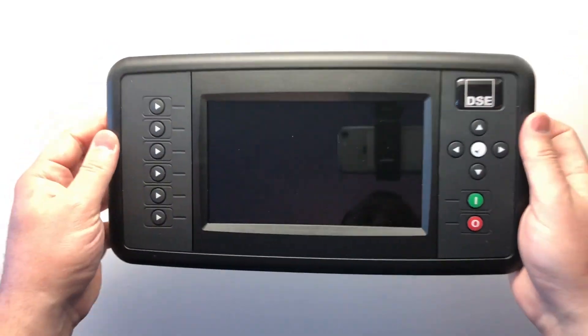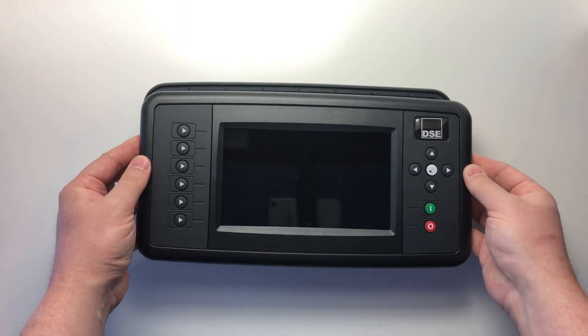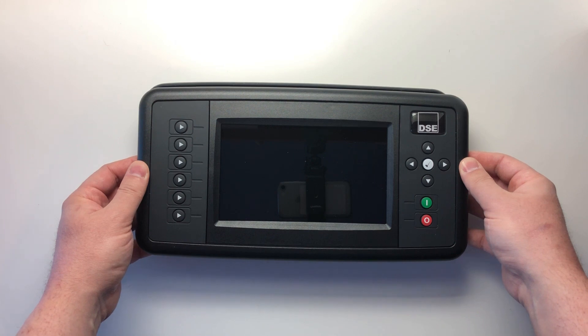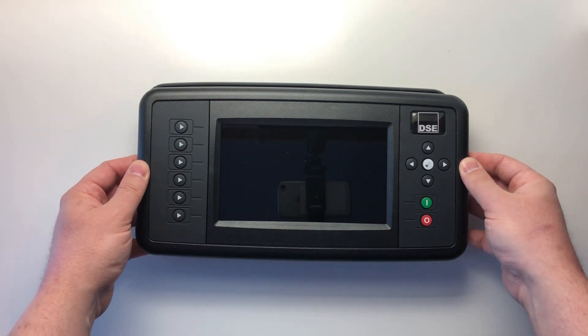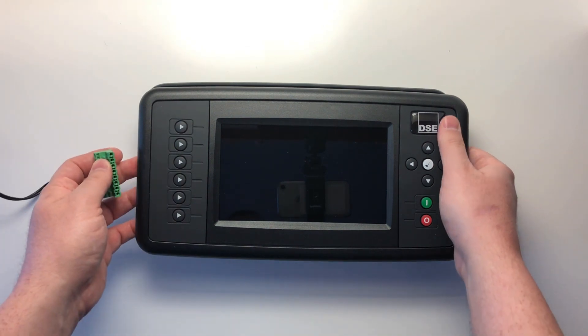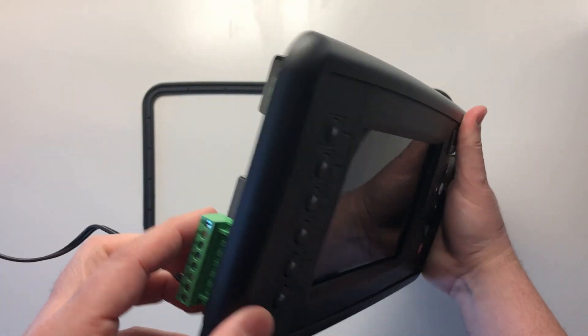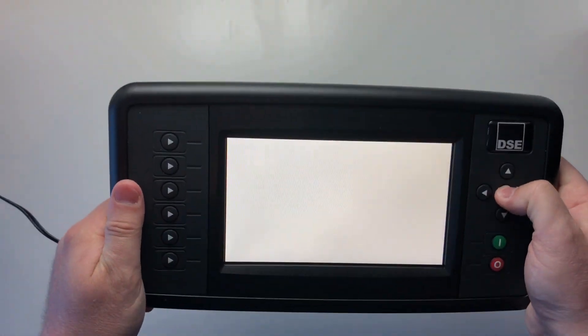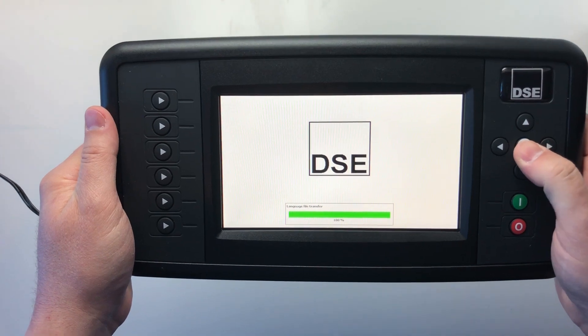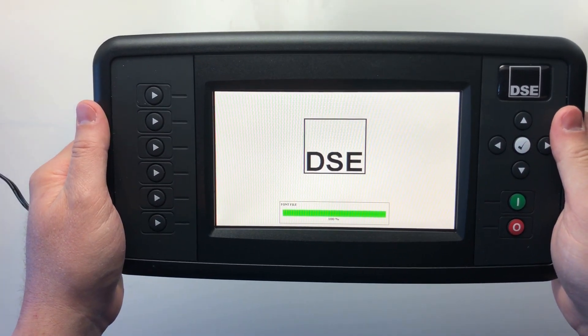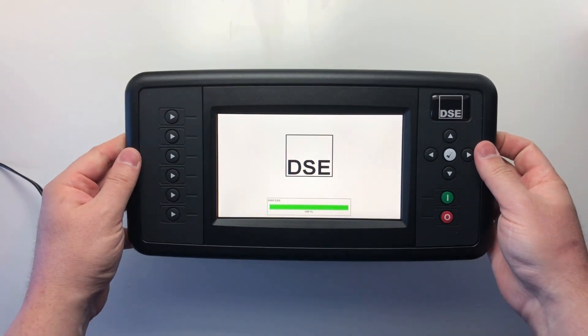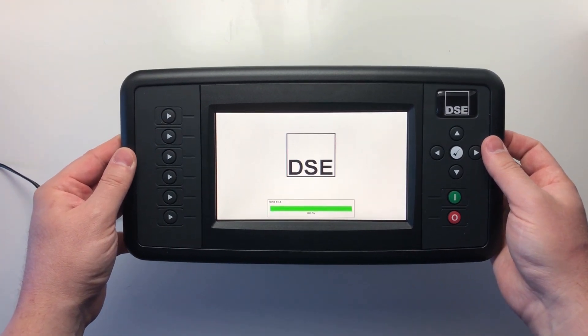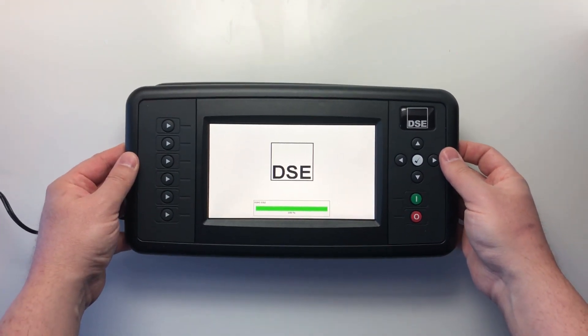The DSE8920 is designed for genset to genset synchronizing or to synchronize a single genset with the main supply. At boot-up, with a simple key press, the user can decide to use the module as a DSE8910 auto-start load share unit or as a DSE8920 auto mains failure load share unit. This delivers additional flexibility and also allows the user to stock a single part for use in a variety of applications.